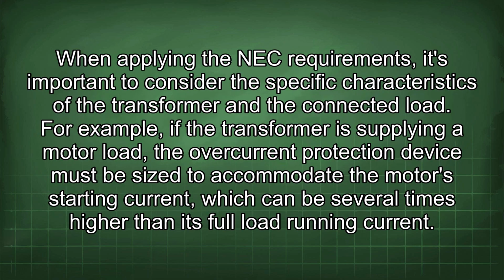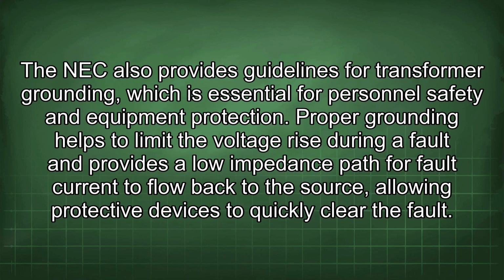When applying the NEC requirements, it's important to consider the specific characteristics of the transformer and the connected load. For example, if the transformer is supplying a motor load, the overcurrent protection device must be sized to accommodate the motor's starting current, which can be several times higher than its full load running current. The NEC also provides guidelines for transformer grounding, which is essential for personnel safety and equipment protection. Proper grounding helps to limit the voltage rise during a fault and provides a low impedance path for fault current to flow back to the source, allowing protective devices to quickly clear the fault.